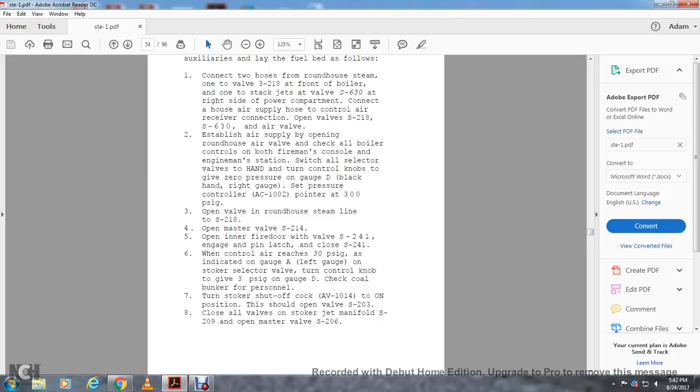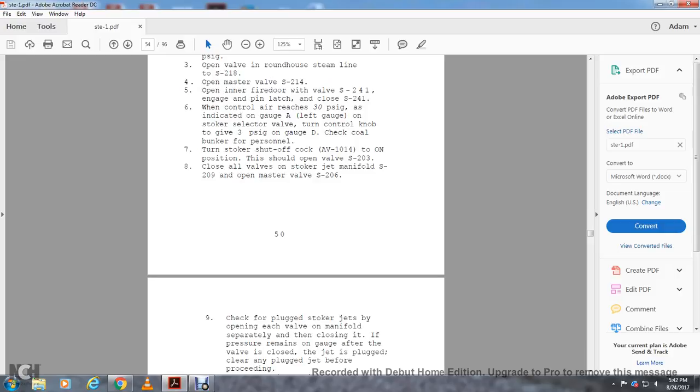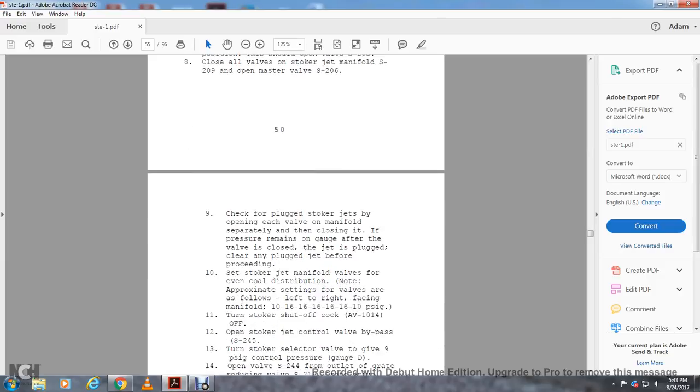Turn the stoker shutoff cock valve AV-1014 to the on position. Open valves S-203. Close all valves on the stoker jet manifold S-209, and open master valve S-206. Check for plugged stoker jets by opening each valve on the manifold separately and then closing it. If the pressure remains on the gauge after the valve is closed, the jet is plugged — clear any plugged jets before proceeding. Set the stoker jet manifold valves for even coal distribution. The approximate setting of the valves, from left to right facing manifold, is: 10, 16, 16, 16, 16, 16, 16, 10 PSI.